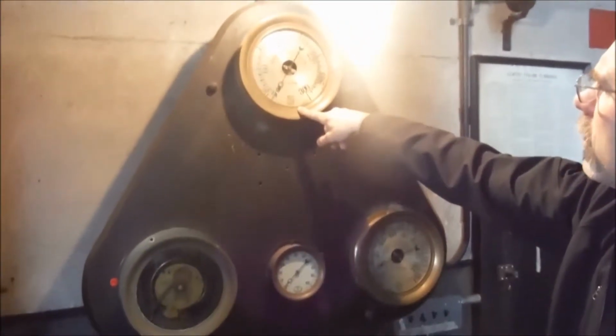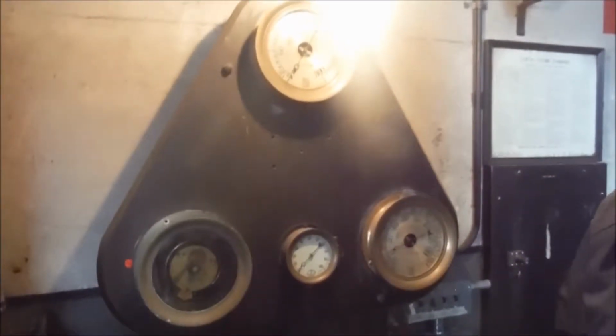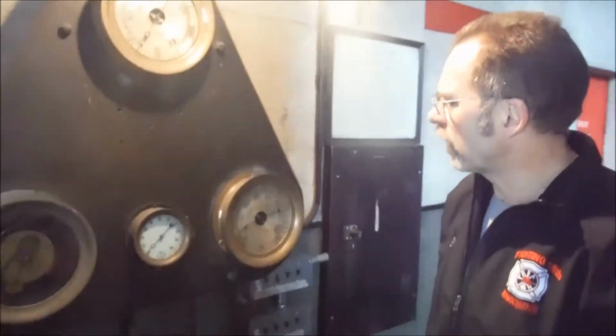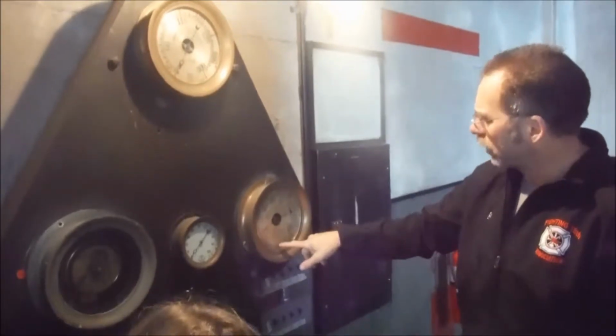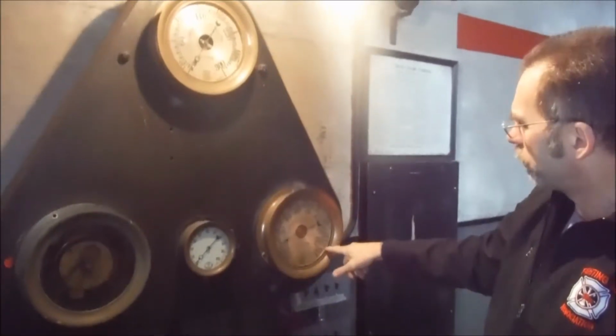So what are the gauges here telling us? Well, that says steam, so I'm sure that's steam inlet pressure from 0 to 300 psi. So that tells me that in the era of this thing, it was considered a high pressure turbine. In fact, I think still in stationary industry, anything over 100 psi is a high pressure turbine. Right. First stage, this is going to be the steam pressure into the first stage of your turbine, or basically what's coming out of the nozzle block into the turbine, right? And you're never going to get the whole 300 psi going in there.